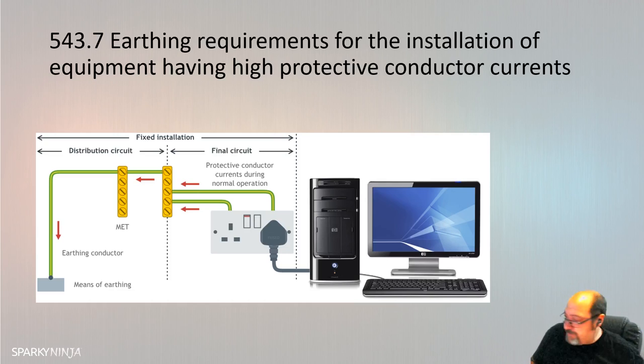The difference being that when I look at a 13 amp plug and socket, and I go to unplug it, I can potentially, in the insertion and removal, touch an exposed part. I can reach the conductive pin, and if there's any current flowing through to that protective conductor and I'm touching a protective conductor, I can experience some sensation through that. However, if it's the 60309, that's obviously inside the hollow of the socket, and I can't, in the action of removal, make contact with that.